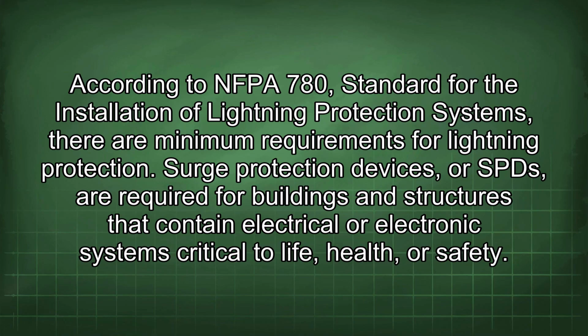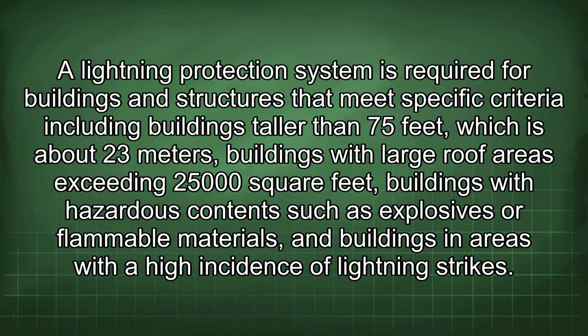According to the NFPA 780 standard for the installation of lightning protection systems, there are minimum requirements for lightning protection. Surge protection devices, or SPDs, are required for buildings and structures that contain electrical or electronic systems critical to life, health, or safety. A lightning protection system is required for buildings and structures that meet specific criteria, including buildings taller than 75 feet, which is about 23 meters, buildings with large roof areas exceeding 25,000 square feet, buildings with hazardous contents such as explosives or flammable materials, and buildings in areas with a high incidence of lightning strikes.